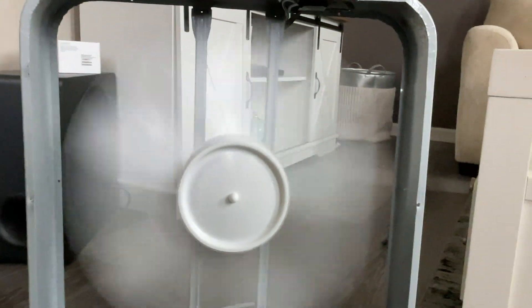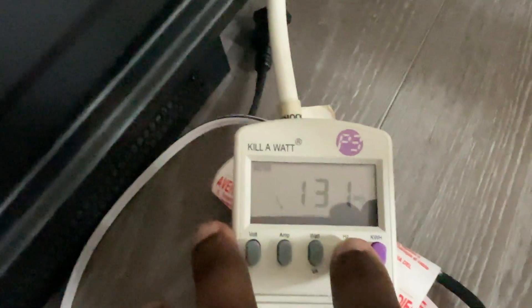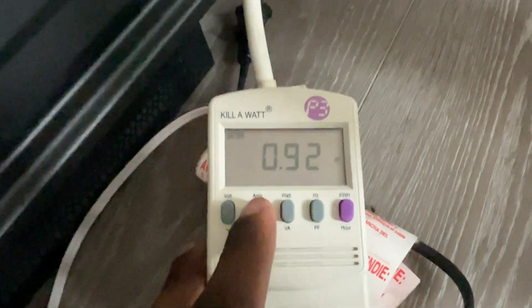Moving a lot of air — that's a lot of air coming out of that fan. On high speed: 1.16 amps, 132 watts. Let's check how efficient it is — the power factor is 0.92, so it's pretty efficient.